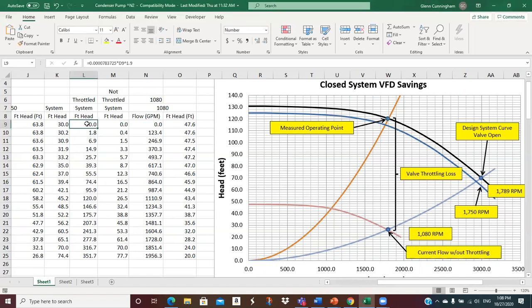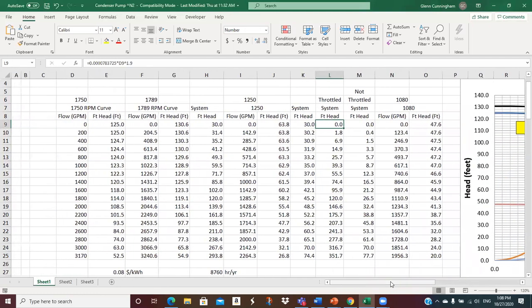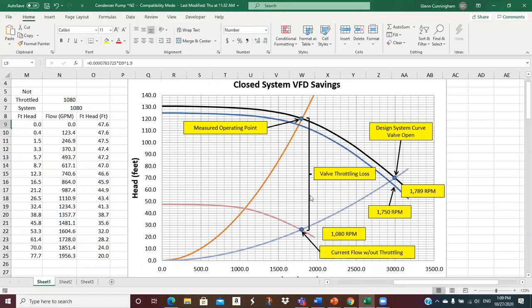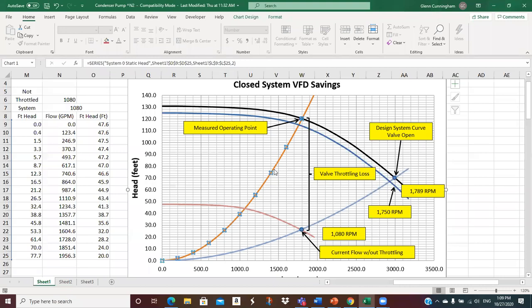So there is no static head, so it's just the flow coefficient times the flow raised to the 1.9 power. And bingo. So I take all of my flows. Doesn't matter which flow, which one. I'm using D9. Okay, I'm using these flows, but it doesn't matter. You could use these flows as well. And you run out your system curve, and then you plot it up. Okay, so my analysis tells me that's where these guys are operating.